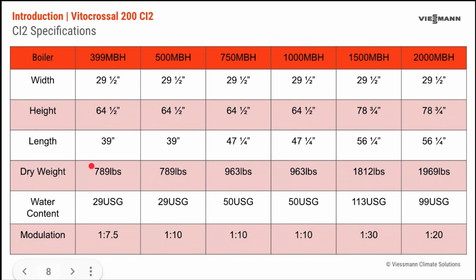Take a peek at the weights, considerable weights here. So we're truly talking about a lot of mass in terms of the boiler and the heat exchanger. This is a high mass boiler. So considerable amount of water, 29 gallons in the 399,000 and the 500, 50 in the 750 and 1 million, 99 in the 2 million, and then 113 gallons in the 1.5 million. Modulation or turndown ratios are listed here. All impressive, but a particular standout here is the 1.5 million at a 30-to-1 turndown ratio.